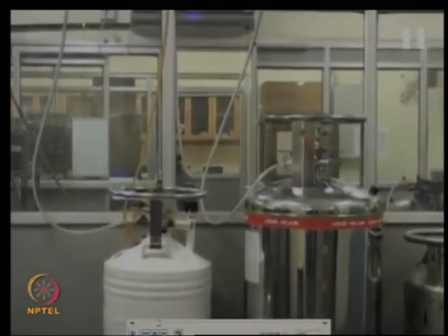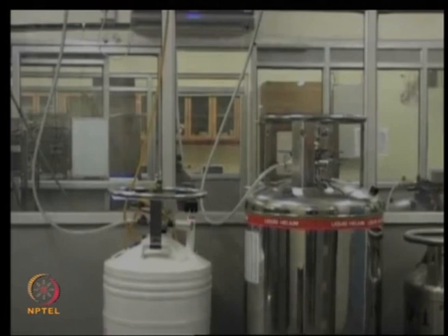From all these things, what you see is there are recovery lines. Some helium will always get evaporated when you are doing experiments, or when you are filling liquid helium to this, or the helium will always get boiled off. So, on every dewar, wherever you see a helium dewar, you will see some recovery line, and the helium which is getting boiled off from this is getting stored in a recovery bag which is stored above this, and we will see that later at the end of this video. Okay. So, these are all the recovery lines where boiled off helium gas will be stored. It is not let go to the atmosphere as what you see otherwise in nitrogen.